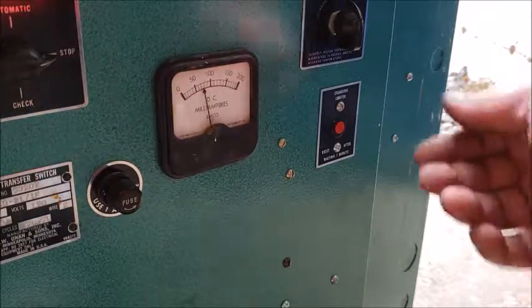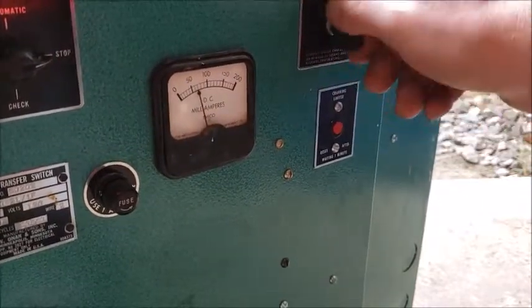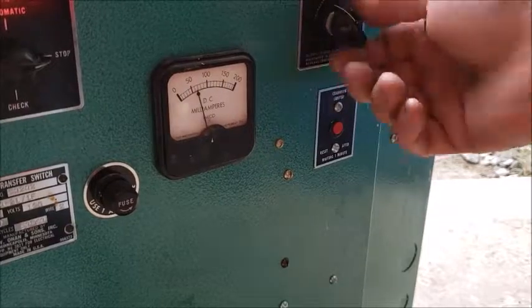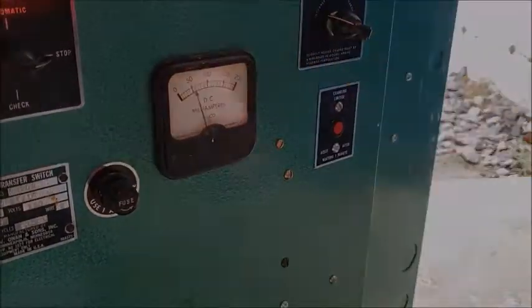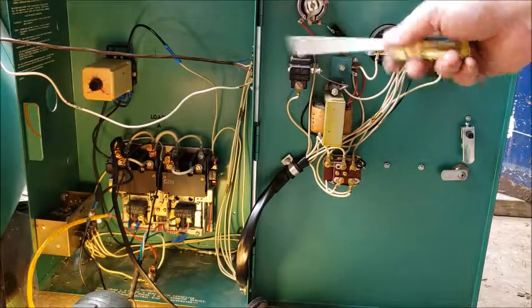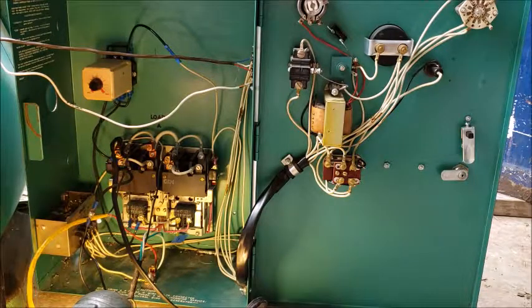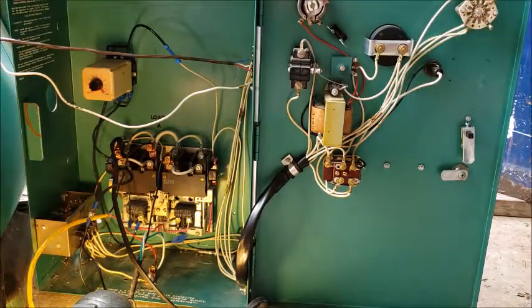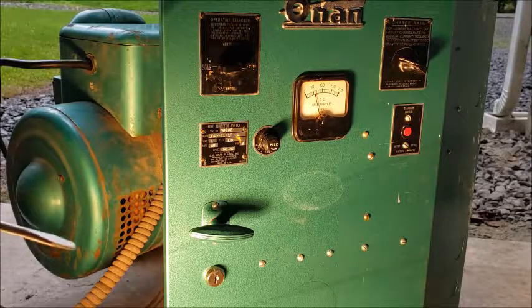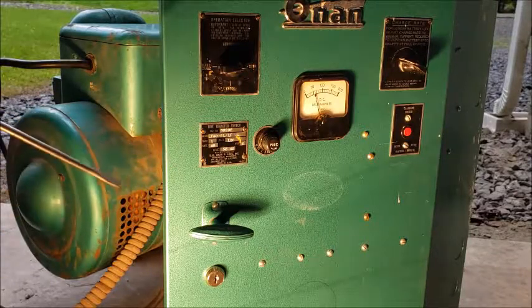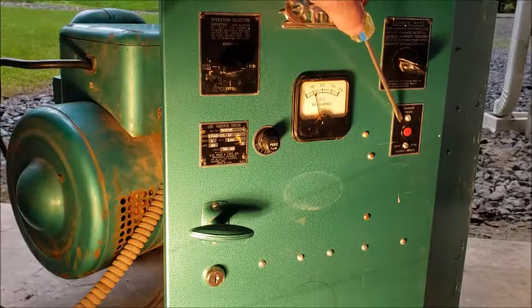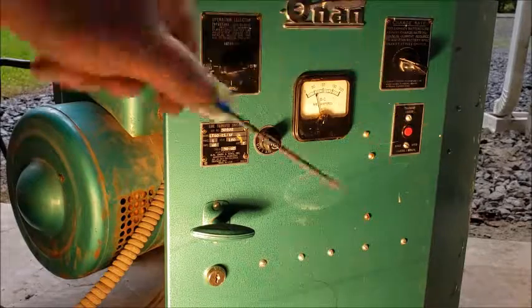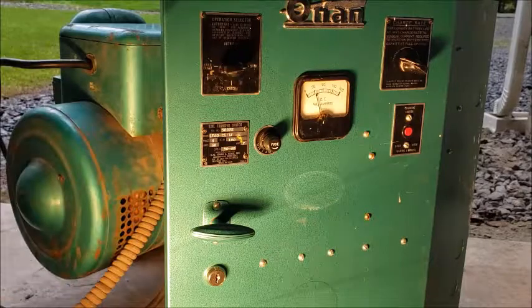This is called an overcrank breaker. And if the engine cranks too long this will trip. Shut the gas off to the generator and ran it out of gas. And so now I'm going to remove the line voltage from the transfer switch and see if this cranking limiter works. After a certain period of time of cranking that red button should pop out.